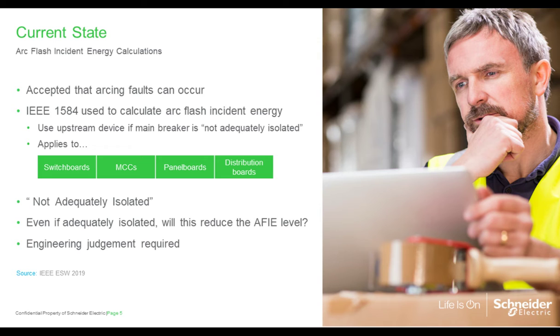Anthony Parsons raised a great question during the IEEE Electrical Safety Workshop a few months ago, addressing what is sufficient isolation between the line side and load side of an electrical enclosure. IEEE 1584 recommends using an upstream device for calculations if the line side isolation is questionable. This situation requires engineering judgment or a certification from the manufacturer in order to decide whether your main breaker is sufficiently isolated. Otherwise, study engineers should label the equipment based on the worst case scenario.